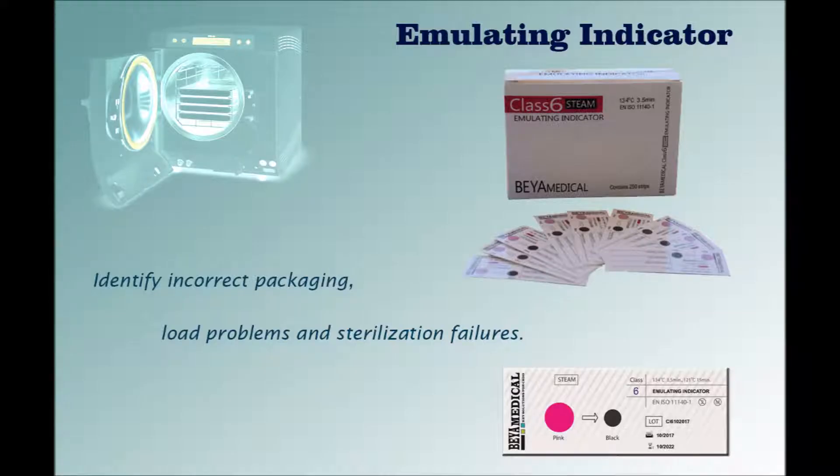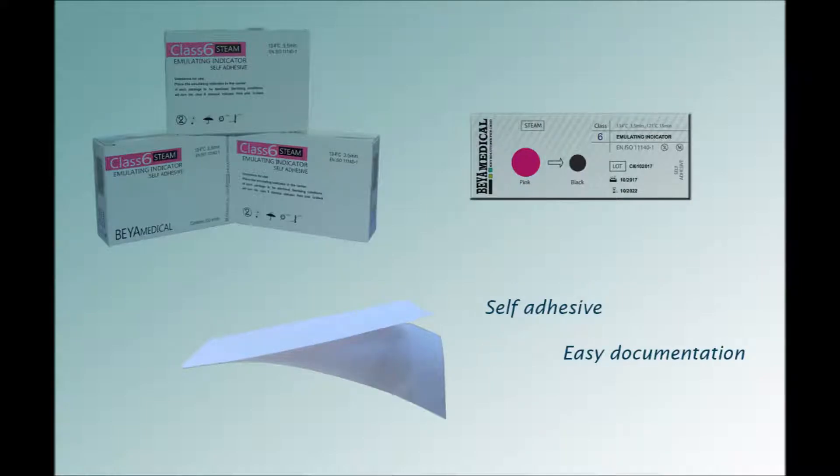BeyaMedical Emulating Indicators Class 6 are cycle verification indicators that confirm the presence or absence of specific time and temperature parameters during a cycle. The product allows the end user to identify incorrect packaging, load problems, and sterilization failures. BeyaMedical also presents self-adhesive emulating indicators for easy documentation.